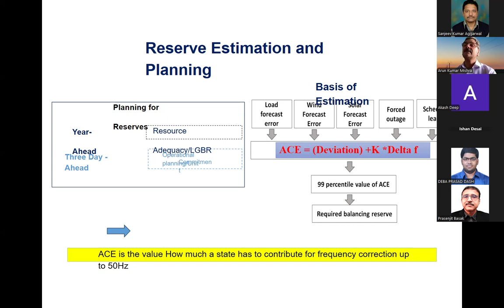When we analyze this, what we find is if we address 99% of the time, overall whatever reserve we keep will be used. If we try to address 100%, that is the 1% extreme event also, that situation may not play out in future and we may not actually use those reserves. So keeping reserve while never using it is wastage of committed resources. So all reserves try to address the 99 percentile of overall area control error historically seen - that's the idea behind it.